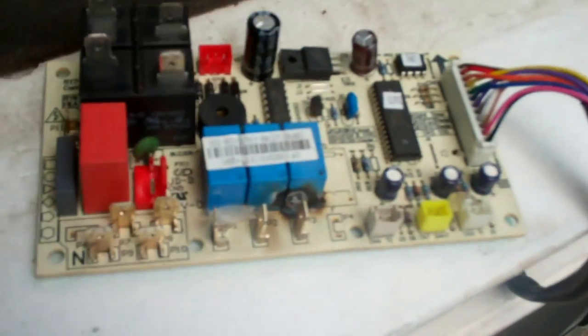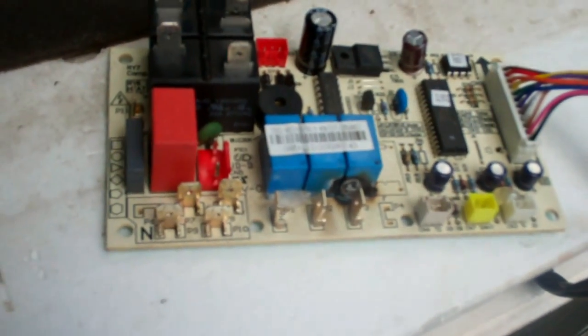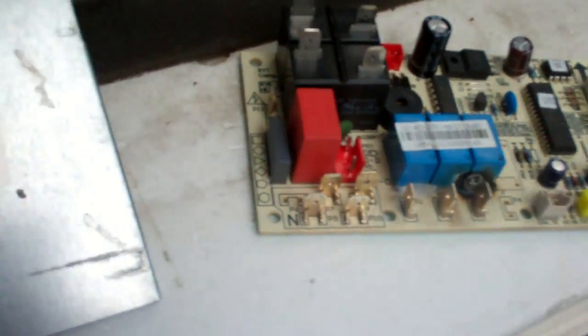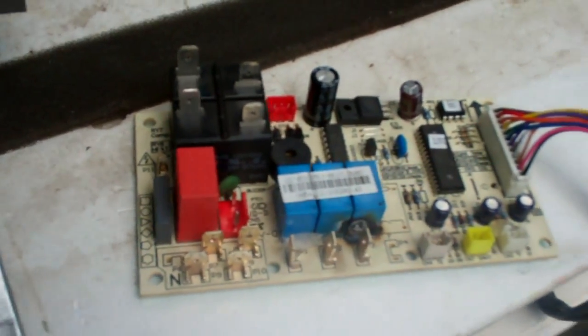There is no RY2, 3, and 4 even identified on the schematic. That helps me a lot. Let's see: P1, 2, and 3, so that's them there. That's for the fan motor. This big capacitor here is for the fan motor as well, so I know that's not the issue.